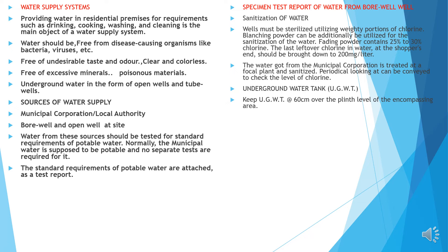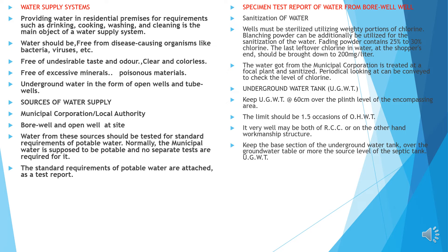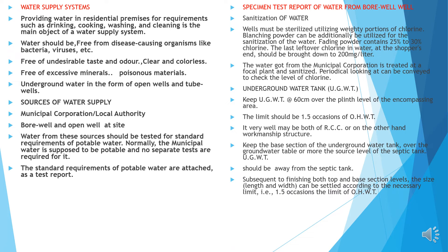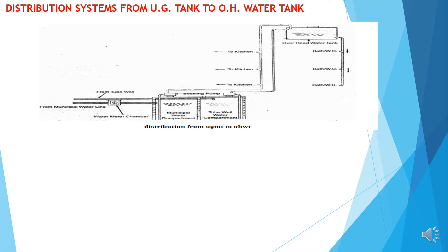Underground water tank: keep underground water tank 60 cm above the plinth level of the surrounding area. The capacity should be 1.5 times that of the overhead tank. It may be built in RCC or brickwork, etc. Keep the base slab of the underground water tank above the groundwater table, and above the invert level of the septic tank. The UG water tank should be away from the septic tank. The size can be settled according to the necessary capacity — that is, 1.5 times the capacity of the overhead tank. A freeboard of at least 15 cm should be given. See this is the image of the overhead tank and how it has been connected, coming to various points and going to the building system.